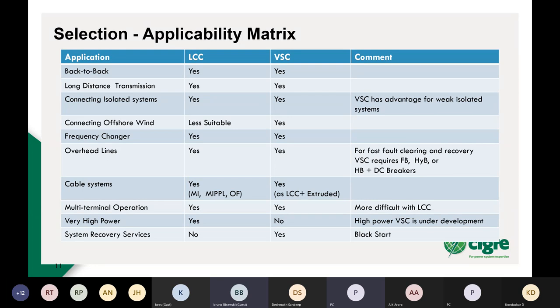LCC has the advantage there because it has very fast fault clearing through control action. For VSC, it requires that you provide either full bridge technology, hybrid technology, or half bridge plus DC breaker technology if you want very fast clearing. For cable systems, either technology can be used with cables. For LCC, it's primarily MI, MIPPL, and OF cables. And for VSC, you can use any cable type as well as extruded cables.